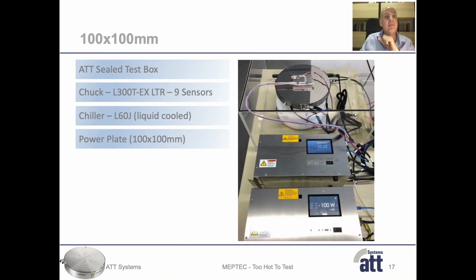So the second example is a 100 by 100 millimeter contact area. We used again our sealed test box, our 300 millimeter LTR chuck with 9 sensors, but we used a smaller chiller, actually with less cooling power, and we used a smaller power plate to reflect the smaller contact area. We used a different chiller because this customer already had an installed base of L60J chillers, and they wanted to see if they can upgrade their existing installed base with the LTR and multisense functionality.